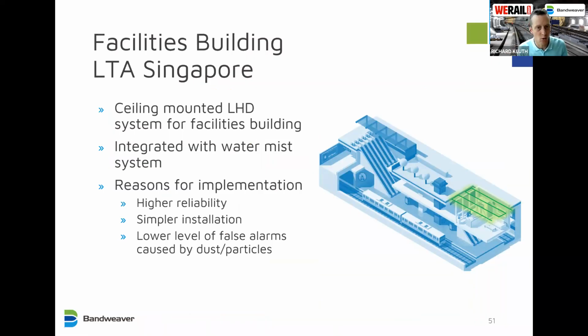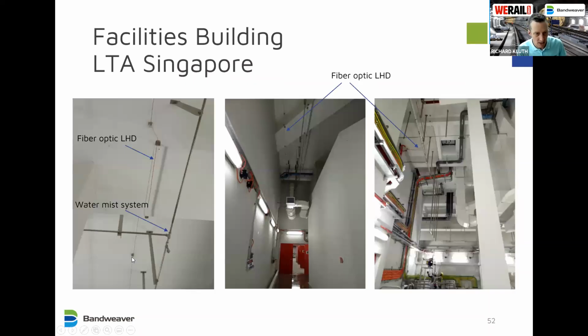The Land Transport Authority in Singapore, they installed the system for their linear heat detection for the facilities building, integrated with the water mist system. And again, it's at ceiling level. And the reasons for implementation over point sensors is very similar to the station and concourse. Higher reliability, simpler installation, lower levels of false alarms caused by dust and particles, which is an issue in these spaces. So here we can see, along the left one, you can see the cable at the ceiling height, and you can see it running in parallel with the water mist system here. And you can see it throughout the facility, different areas, different heights. Again, with the different smart zones, you can really divide this up and fine-tune the alarms to how you want to for each section. Really powerful and versatile technology.